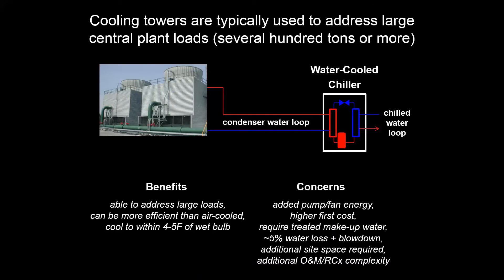You can address large loads when you're using a cooling tower. It can be more efficient than just an air-cooled chiller, and you can have a little bit more control as far as what loads you're able to get rid of — what the capacity is of that chill water system at the same ambient wet bulb and dry bulb conditions. Some drawbacks include added pump and fan energy, and a higher first cost for the extra infrastructure, as well as more treatment needed.